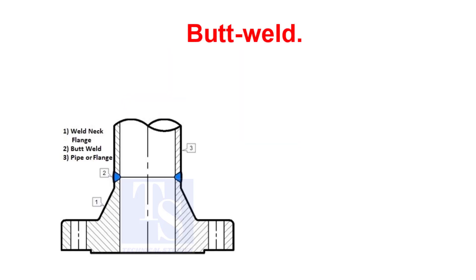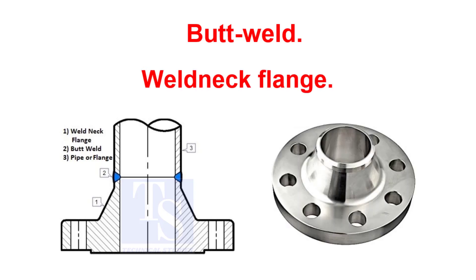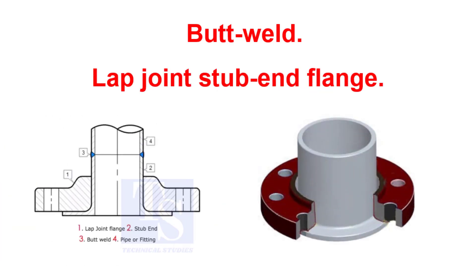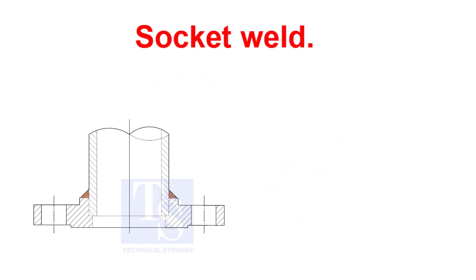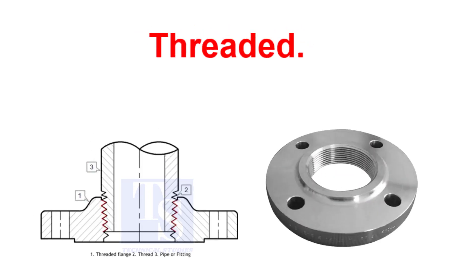Butt welded: weld neck flange is considered the best designed butt welded flange available in the piping industry. Another example of a butt weld joint is the lap joint stub end flange. Socket weld flanges use only one fillet weld on the outer side of the flange. Threaded flanges are joined to pipes by screwing the pipe and are used on piping systems that prohibit direct welding on the pipe. Usually, threaded flanges are used for galvanized piping.